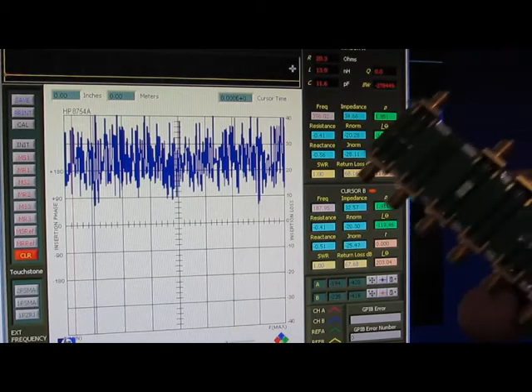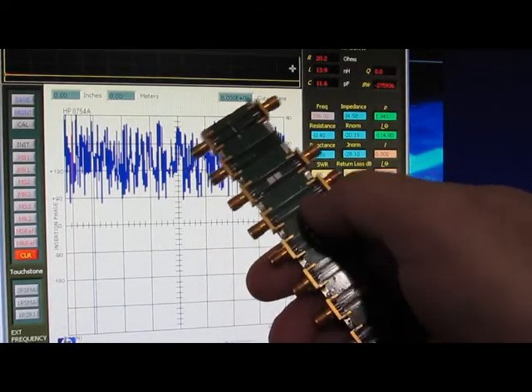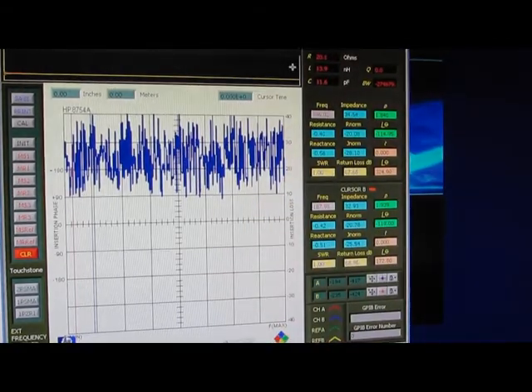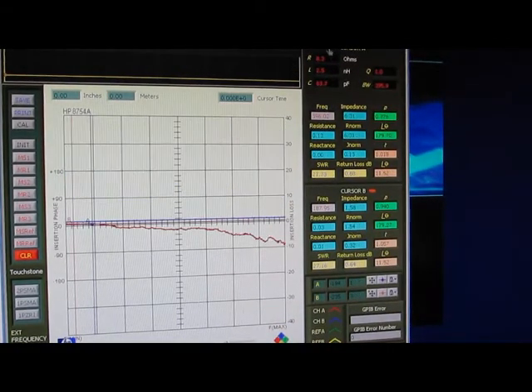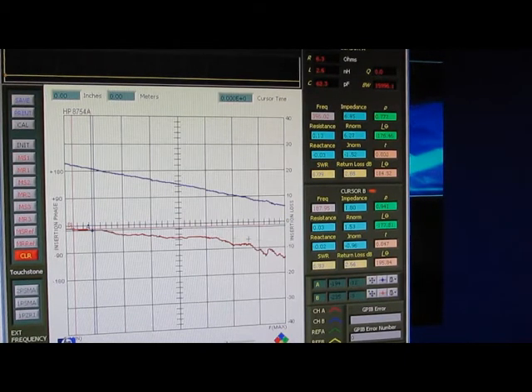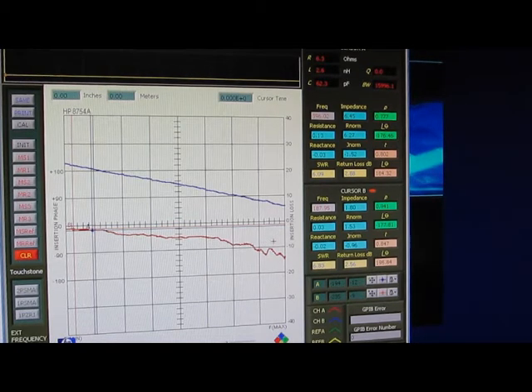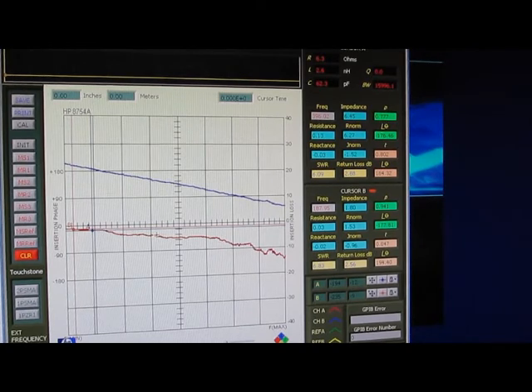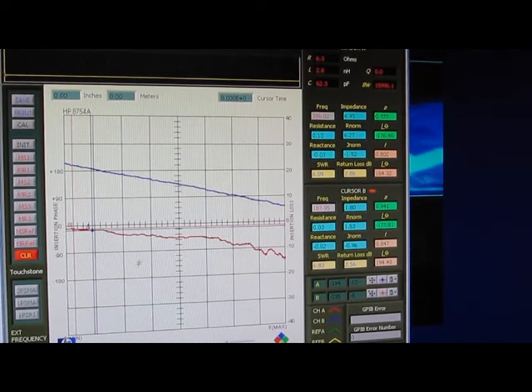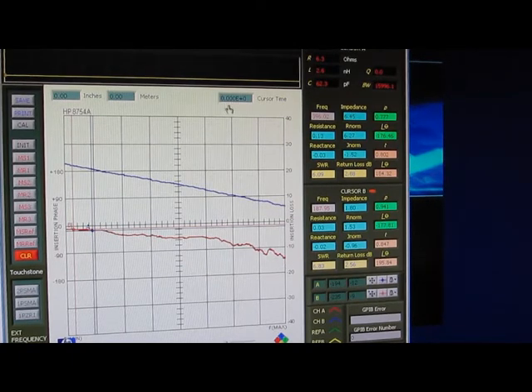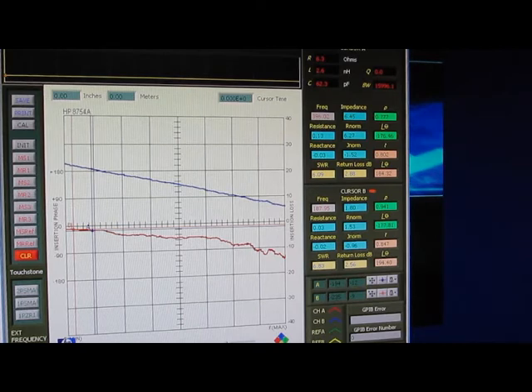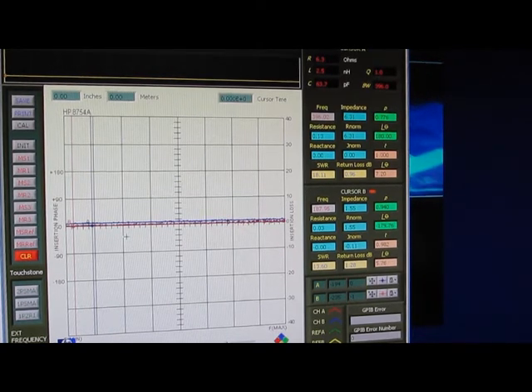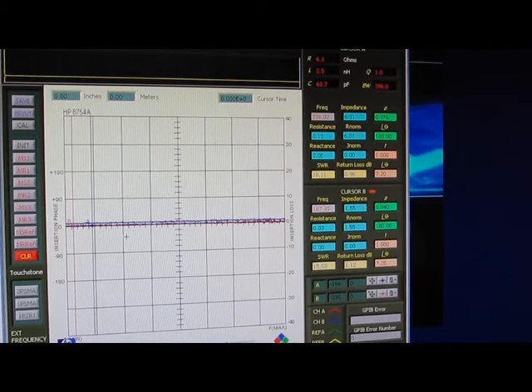Next what I'd like to do is look at the transmission. And again all I'm going to do is install this through here. I've set the network analyzer up for 2.5 dB per division. The through has been installed and the vertical has been set to 2.5 dB per division. So the blue is looking at the phase. The red is looking at the transmission through it. Again the sweep is all the way up to 2.6 gigahertz. What we want to do is calibrate this now. Now that the unit has been calibrated let's go ahead and install the probe.